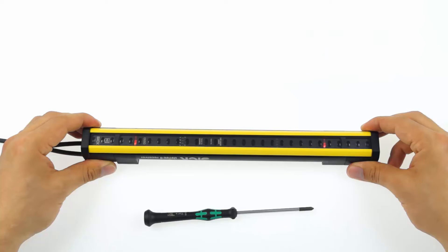Here the beam coding configuration is uncoded, but if you want to use code 1 or code 2, you can directly set the DIP switches to the corresponding positions during the third step. This process has to be repeated for every single device in your system. Make sure that they are disconnected from the power supply as well as from all other devices during the whole procedure.